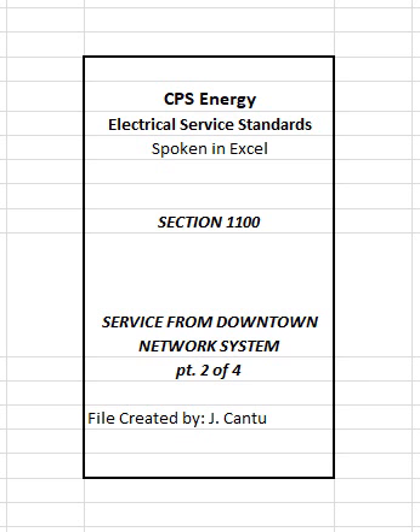5. Transformer vault or room penetration of secondary grid or service lateral conductors shall be a minimum height of 42 inches and a maximum height of 60 inches from the floor level inside of the transformer vault or room. Customer shall coordinate with the CPS Energy customer service representative on exact location and methods of penetration of secondary grid or service lateral conductors. Final design shall be submitted to CPS Energy for approval.